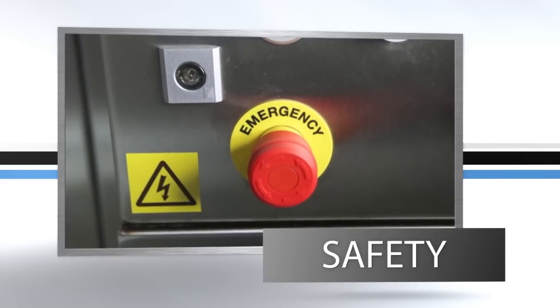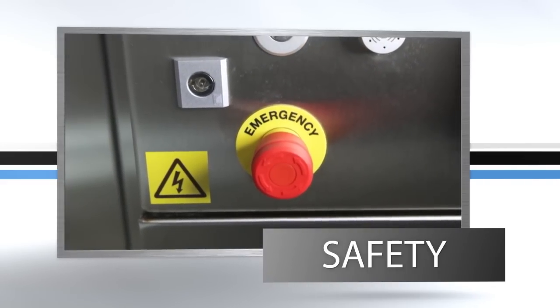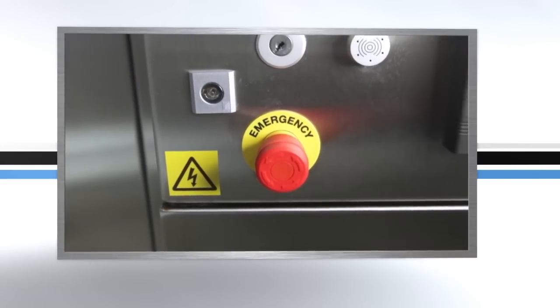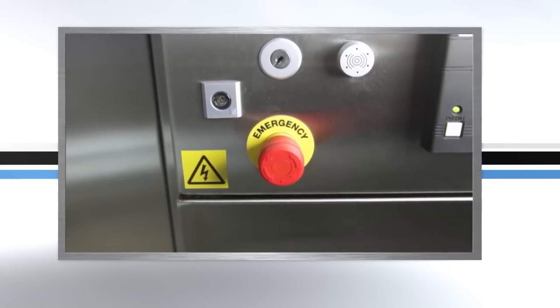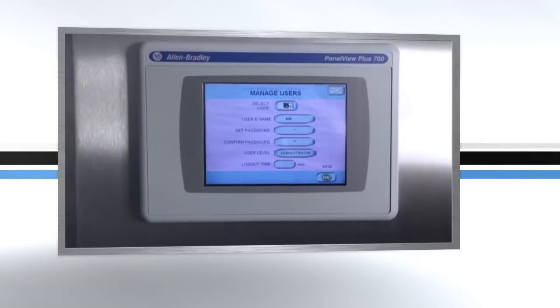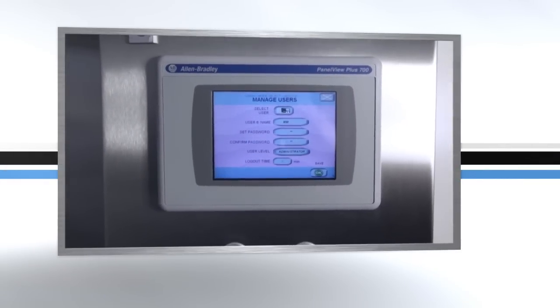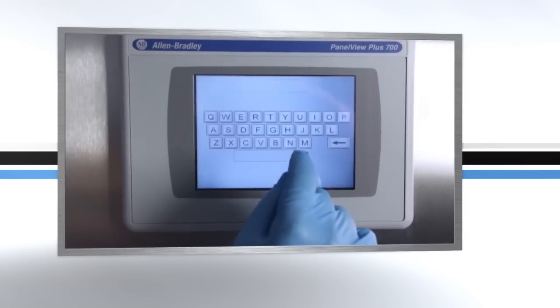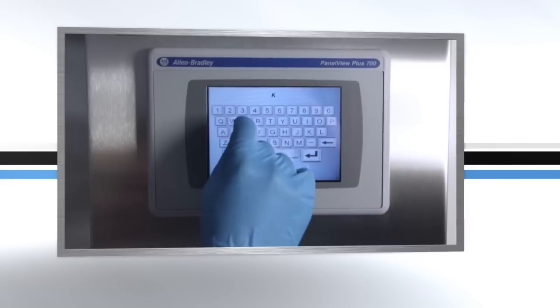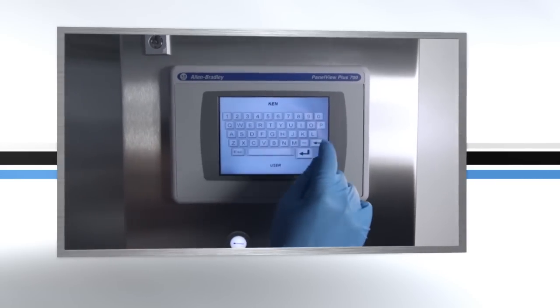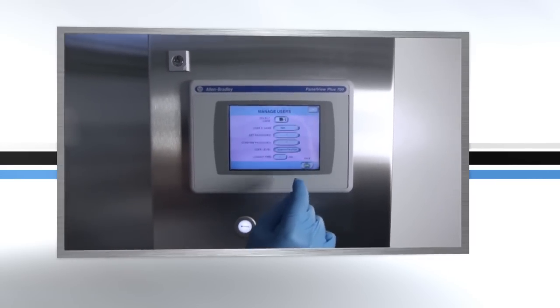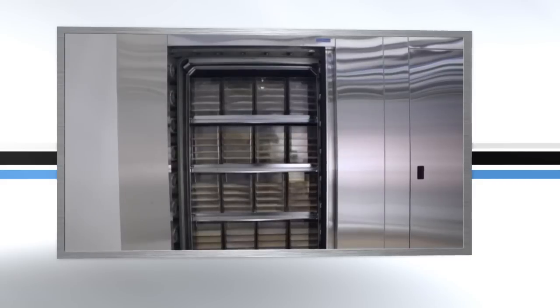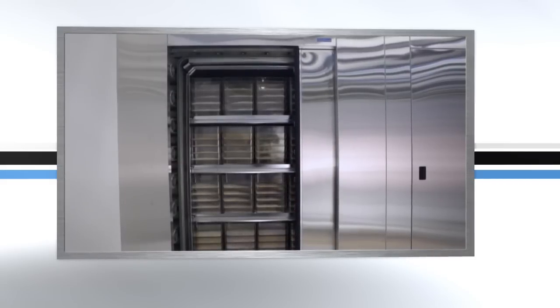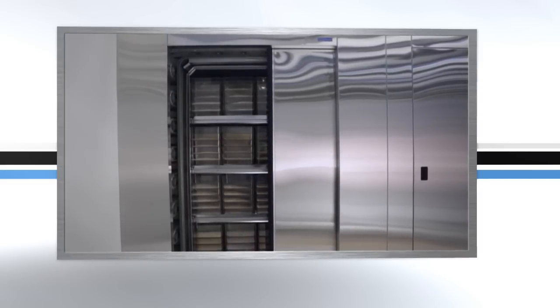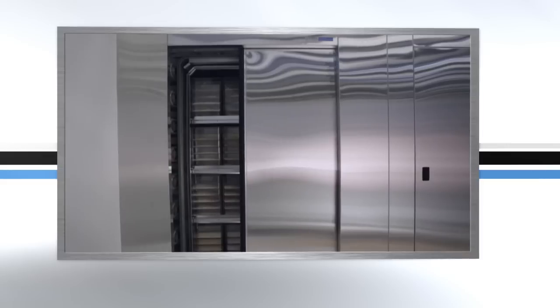At Steris, safety is of paramount importance. Therefore, the AMSCO LSS is equipped with a number of standard safety features. These standard features include emergency stop buttons, security access codes, door sensing devices to prevent injury, door interlock features to allow only one door to be open at a time, and finally, sensors that prevent steam flow while the door is open, as well as prohibit the door from opening while the chamber is pressurized.